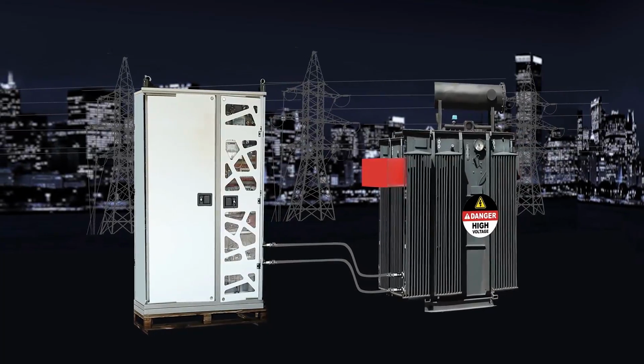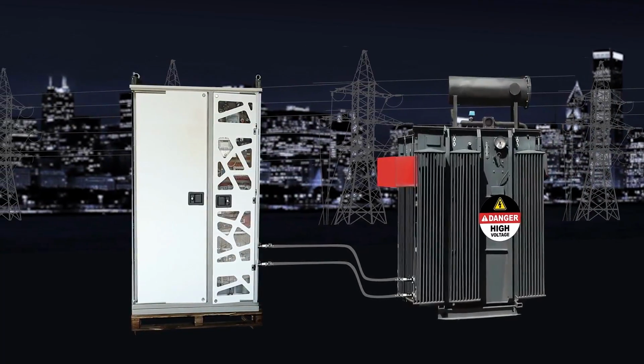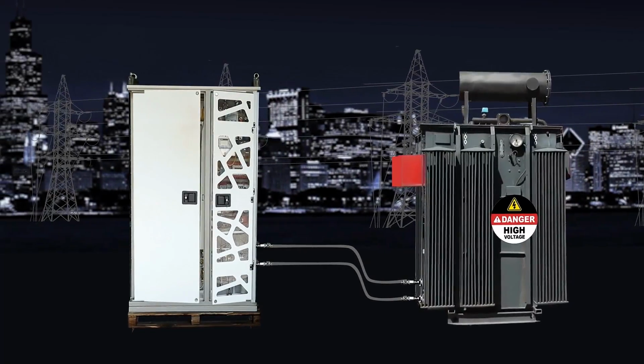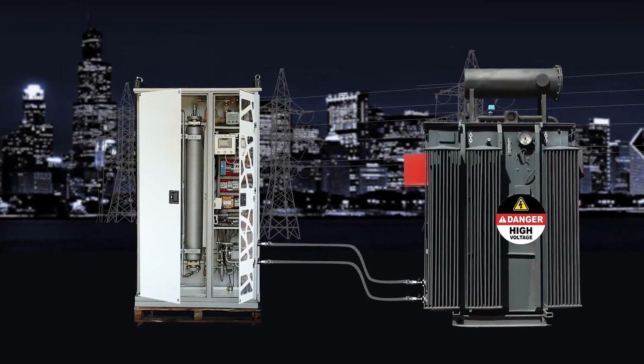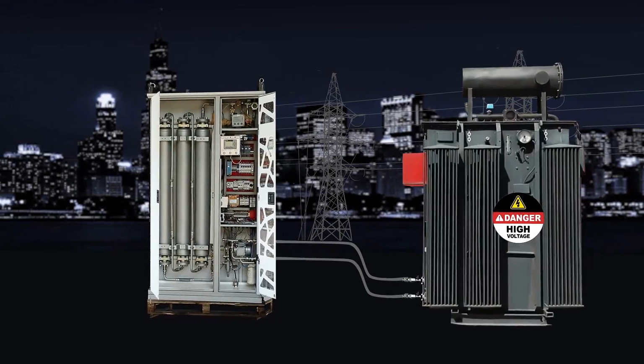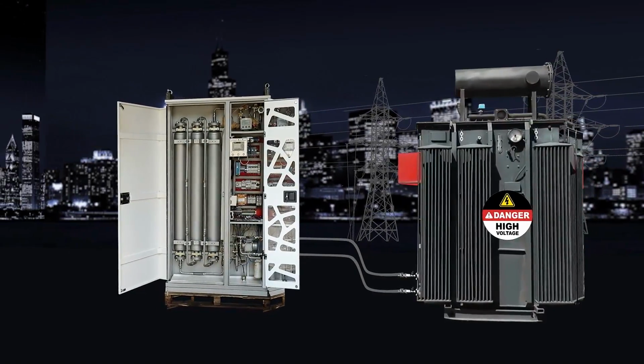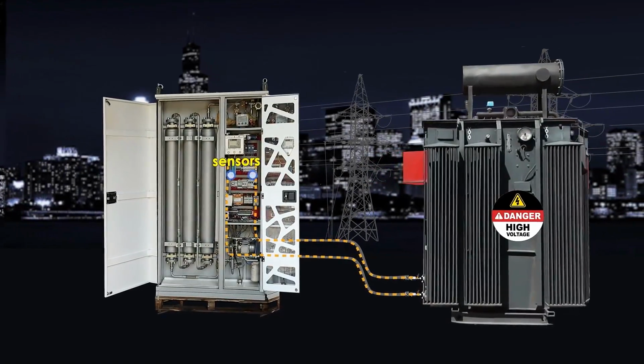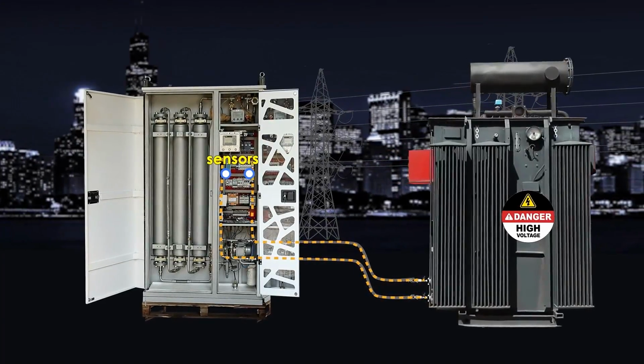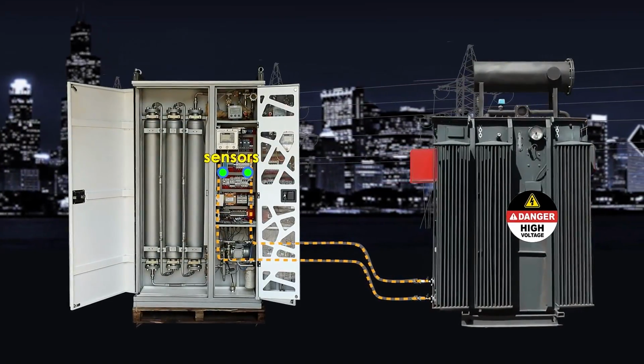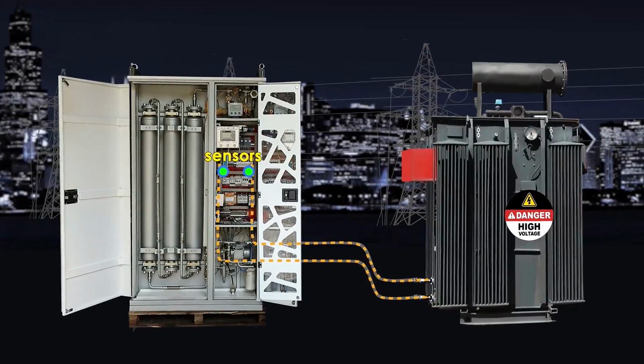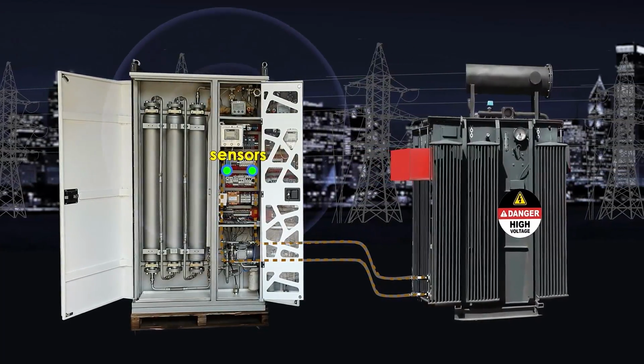These are the features of the basic TOR model. But if desired, the functionality of the equipment can be expanded further. Sorbent drying does not affect the gas content of the oil, and the system software allows the installation of additional sensors for the analysis of dissolved gases, for example, hydrogen, when periodic drying and filtration are not sufficient to keep the oil in good condition.